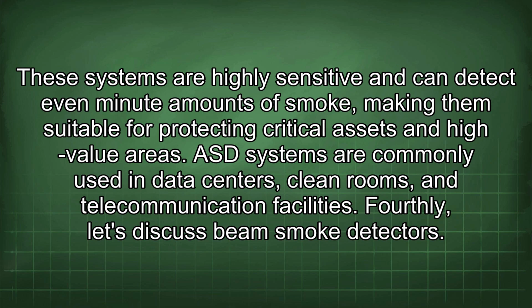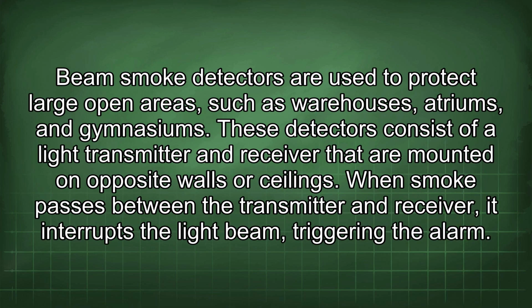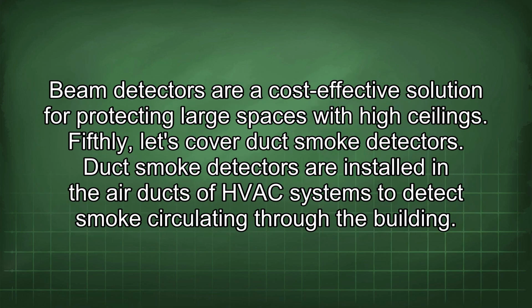Fourthly, let's discuss beam smoke detectors. Beam smoke detectors are used to protect large open areas such as warehouses, atriums, and gymnasiums. These detectors consist of a light transmitter and receiver that are mounted on opposite walls or ceilings. When smoke passes between the transmitter and receiver, it interrupts the light beam, triggering the alarm. Beam detectors are a cost-effective solution for protecting large spaces with high ceilings.